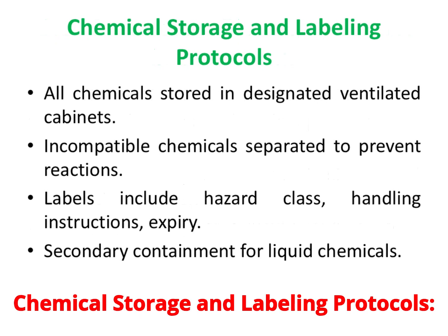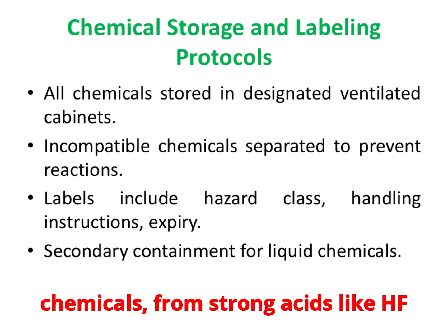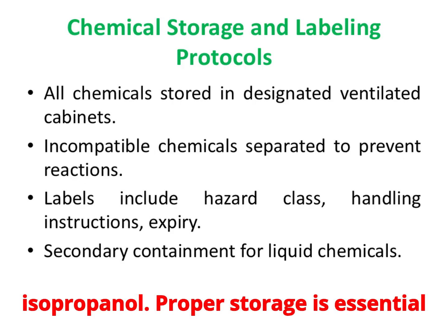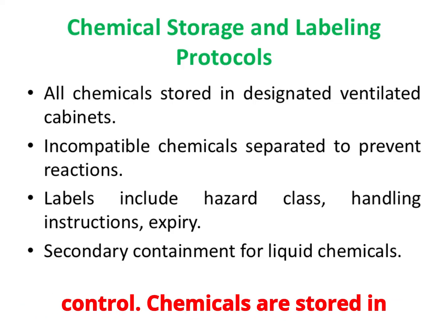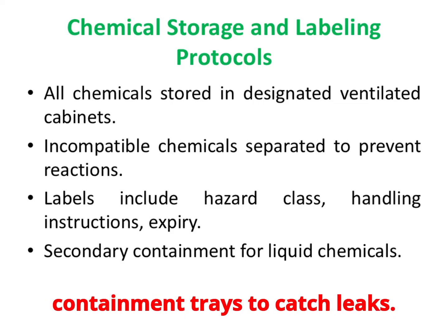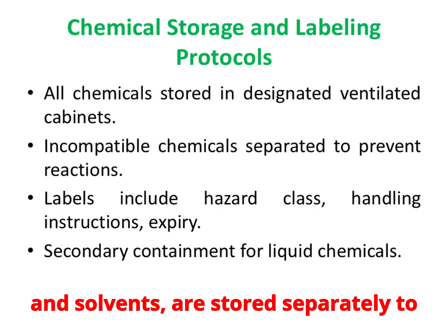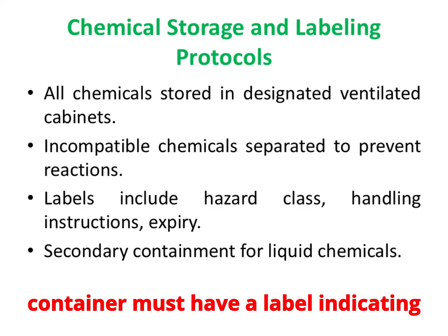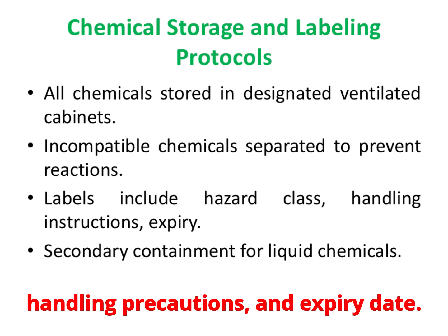VLSI fabrication involves many hazardous chemicals, from strong acids like HF and H₂SO₄ to solvents like acetone and isopropanol. Proper storage is essential for both safety and contamination control. Chemicals are stored in ventilated cabinets with secondary containment trays to catch leaks. Incompatible chemicals, such as acids and solvents, are stored separately to avoid dangerous reactions. Every container must have a label indicating its chemical name, hazard classification, handling precautions, and expiry date.